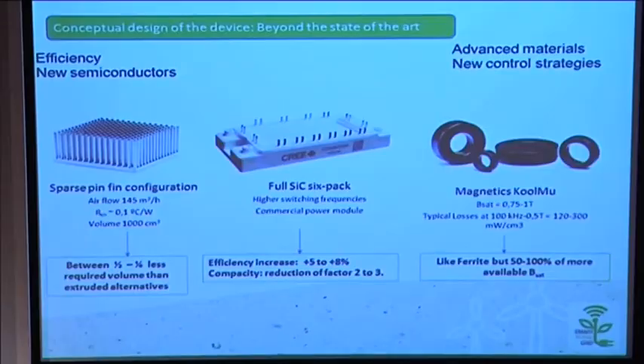We also included the use of a full silicon carbide commercial 6-pack unit for the semiconductors. This means we can use high switching frequency, increasing efficiency by 5 to 8% compared to conventional silicon options, and reducing the required volume by a factor of 2 or 3.